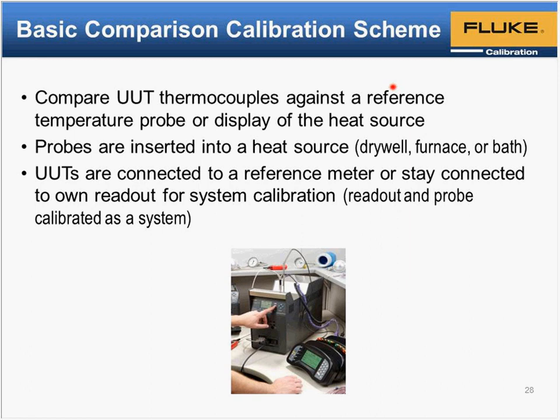The comparison calibration scheme is where you compare the unit under test thermocouple against a reference temperature probe, or possibly the display of a calibrated heat source. Typical heat sources used for thermocouple calibration are dry wells, furnaces, and baths, and we'll show some more pictures here. The one shown here is a dry well type, meaning there is no liquid used inside the unit. It's just a metal block with holes drilled into it to accommodate the thermocouple probes.